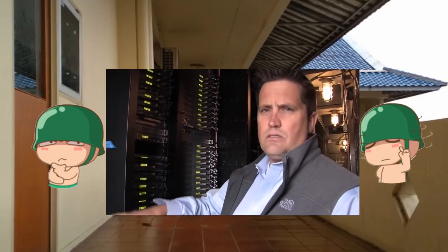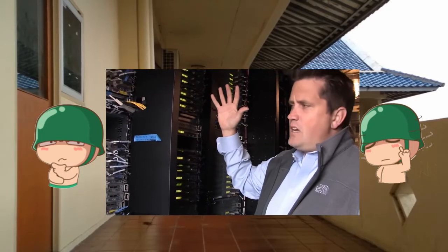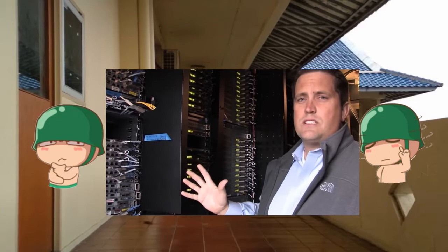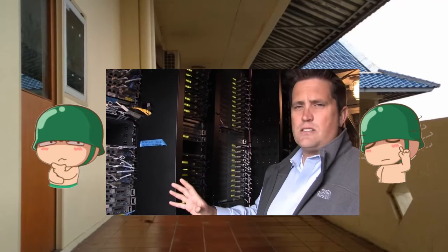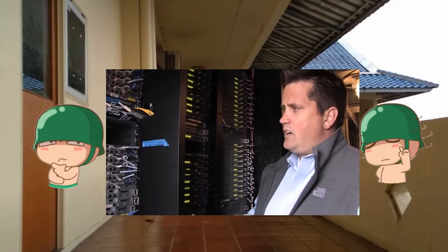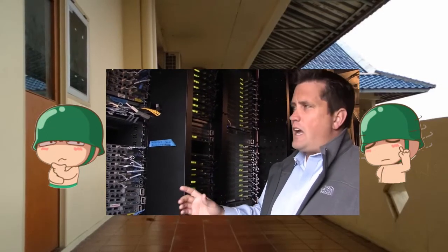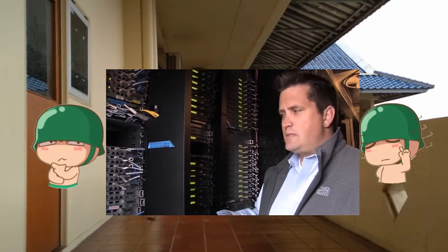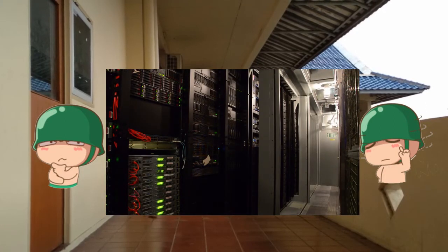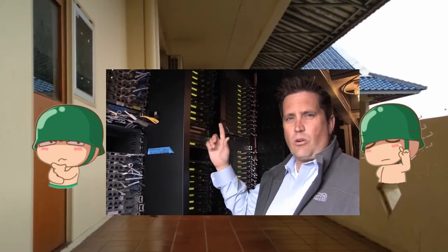So what we have is a fully vertical solution, all the way from the IT itself to the modular data center. That allows us to remove fans from the systems themselves. In each of these racks, there are no fans in the servers. The only fans present are in any networking gear that requires them. That removes that burden from each server and lets us apply it to more IT in our module. Effectively, we're making our modules more power dense and removing elements that decrease efficiency. By not having fans at the small scale, we utilize fans at the large scale, in our air handler.